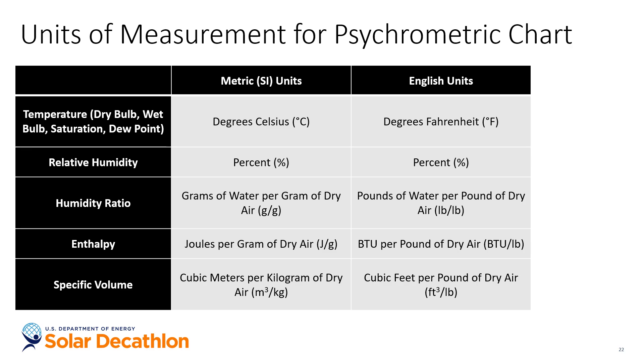I want to acknowledge that the psychrometric charts used in this episode are expressed in SI or metric units. In the United States, it's more common to use English units. We've provided a table showing the terms in both systems. Note that absolute and relative humidity are expressed as ratios or percentages, so the values are the same in either system. One notable exception: in the English unit system, absolute humidity is sometimes measured in grains of moisture per pound of dry air. There are 7,000 grains in a pound — so a humidity ratio of 0.01 equates to 70 grains of moisture per pound of dry air.